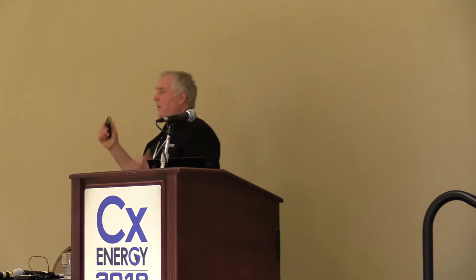So I get downstairs and I get into the main area that they have in the parking area, and I look at their air compressor, and they had about a 30 or 40 horse air compressor. I guess it might have even been a little bigger, but let's say 40 horsepower air compressor, and it was at 110 PSI. And I'm going, wait a minute, guys, I'm in an office building. Why in the world do I need 110 PSI? And the people there didn't know.